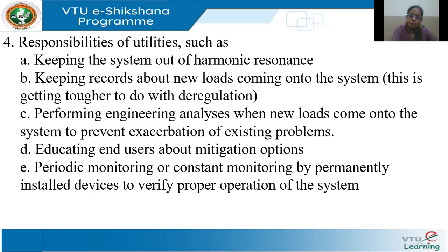The second important responsibility of the utility is to keep track of the records of the loads being connected. Okay, I have a feeder. One industry is connected. Already there is some load. Another new industry comes up. This industry may have some induction furnaces. They may have some welding equipment, etc. The other loads which are already there may get affected. Or, I have a transformer which will take the load of this industry, but my relay I have set to the old loads.